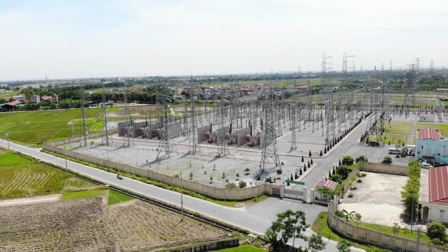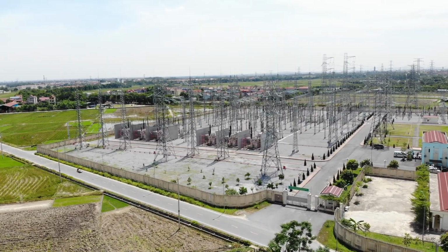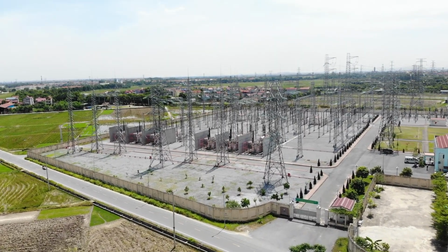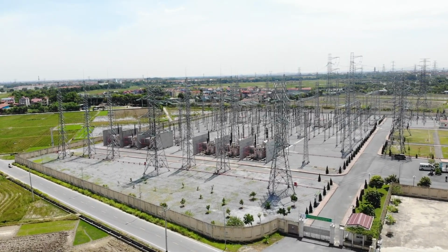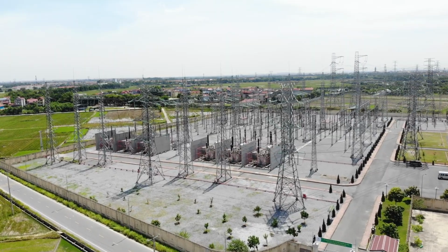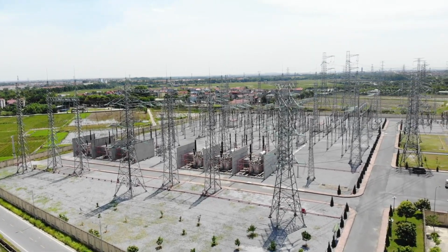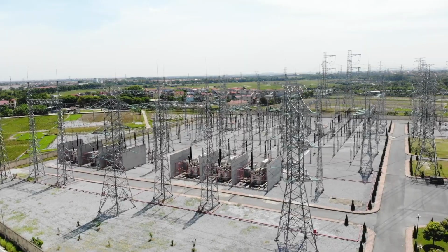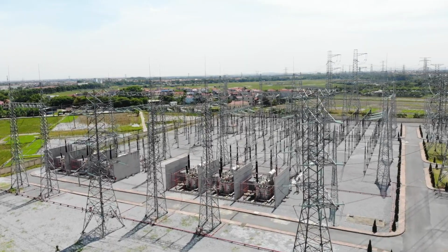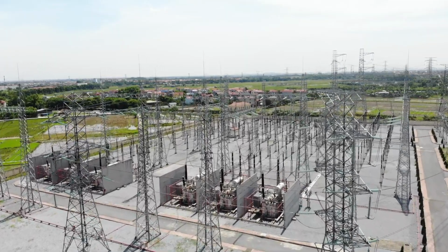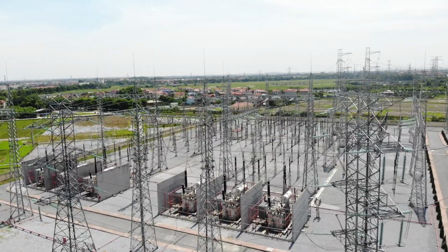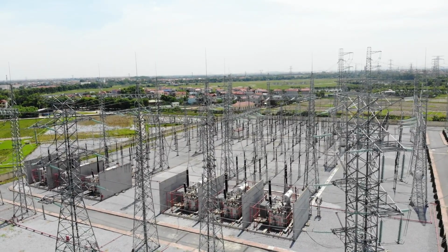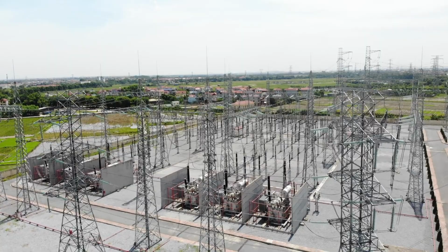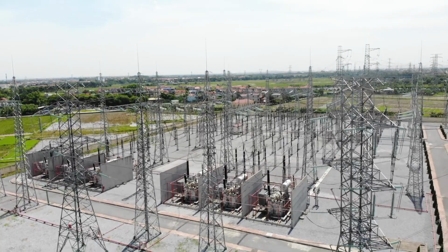One of the main functions of a substation is circuit switching and isolation. Large cities are usually supplied by multiple transmission lines. If one of these lines develops a fault or requires maintenance, operators must isolate it without shutting down the entire system. This is done using devices called disconnect switches, which safely separate parts of the grid while allowing electricity to continue flowing through alternative paths.